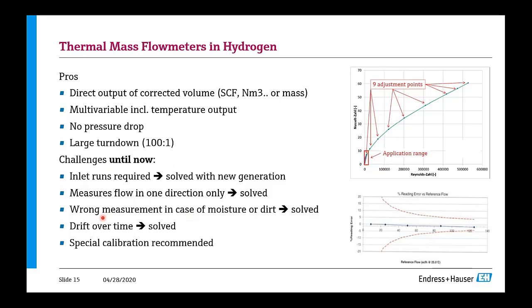That's one challenge solved, so you can improve the accuracy. This is what you see here, a calibration on hydrogen. The challenges till now were that you need a lot of inlet runs with thermal mass. Here we will have a solution with our next generation. They measure flow in only one direction. In a hydrogen generator cooling solution, you would like to know whether the hydrogen is sometimes coming back. This is something we can do in the future. You get wrong measurements in case of moisture or dirt. This is also solved in the future with our Heartbeat Technology. And the existing technologies all tend to drift, but there we have a solution as well. The special calibration, however, will still be a requirement in the future. However, I must say, if you don't calibrate, the repeatability is still good with these meters.